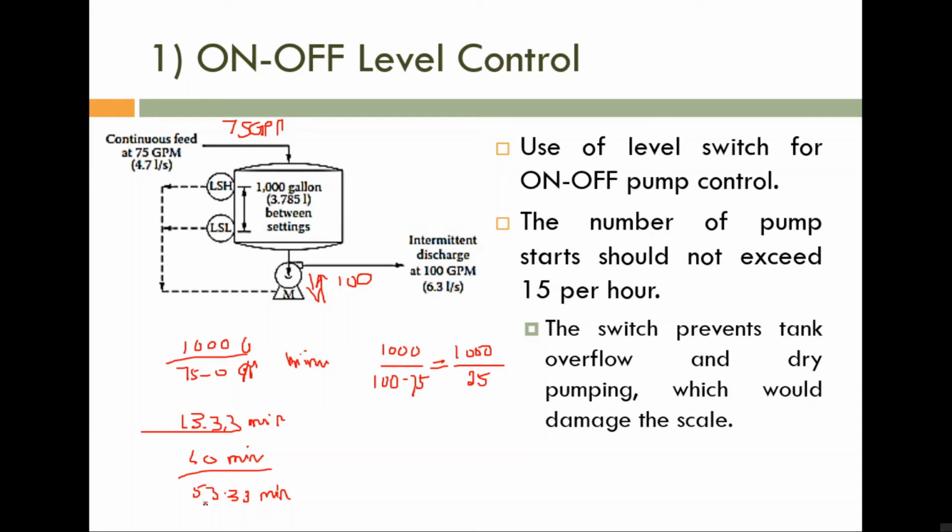So after 13.33 minutes the pump is started. Then after 40 minutes the pump is switched off. Then again after 13.33 minutes the pump is started again. This means the number of starts per hour is roughly 1. Normally 1, rarely 2. Is it okay? What happens if the tank size is 100?